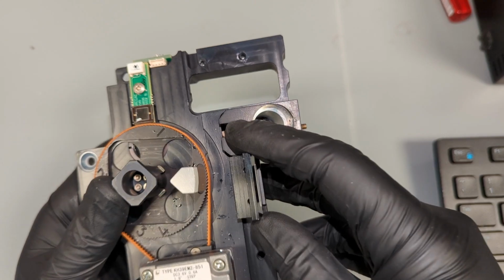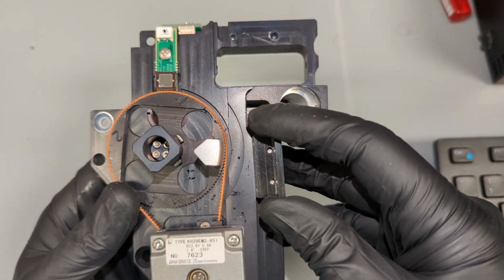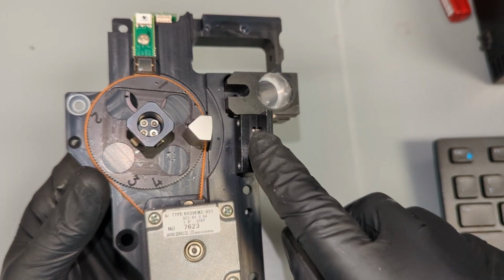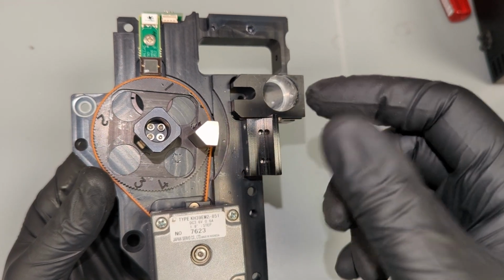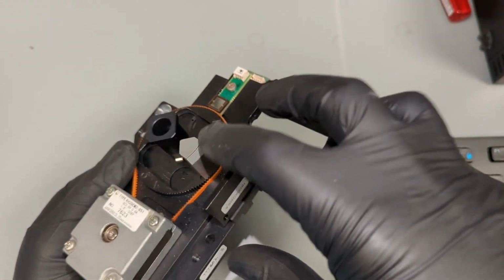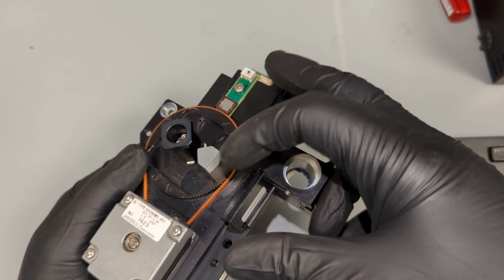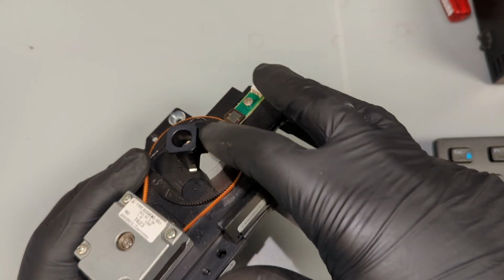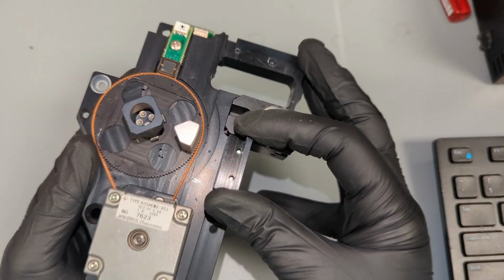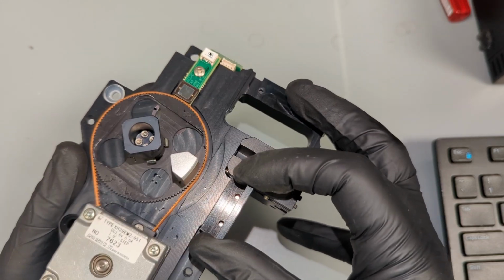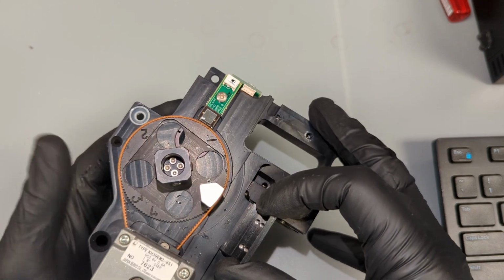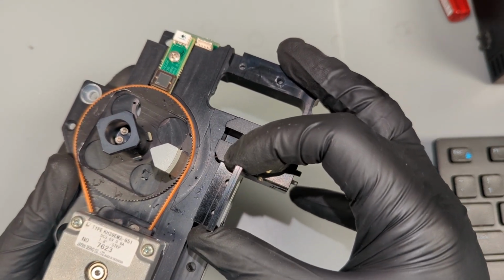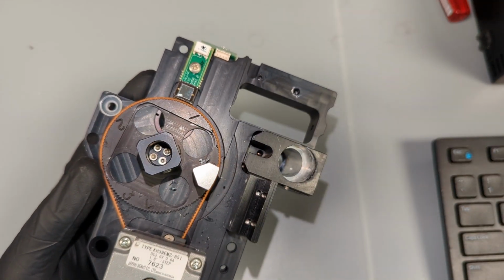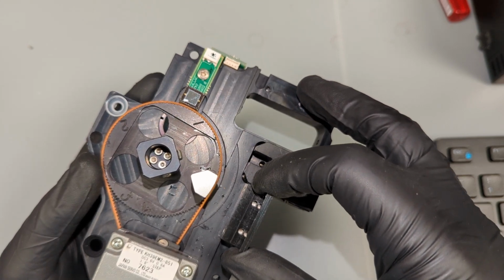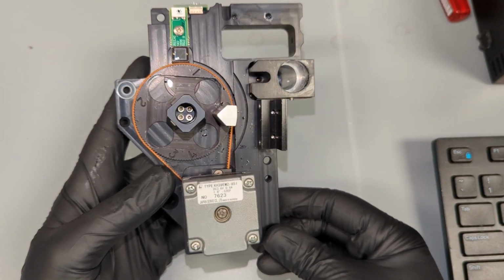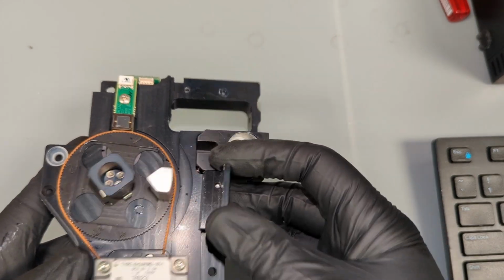Now, what can happen with these, and it's definitely happened with our instruments, you can see here that you can actually adjust the angle and positioning of this. And again, try to picture this. There is a daughter board here with a barcode reader IC there. So it will emit infrared light that will bounce off of this white plate or the barcodes, and then will be reflected back to this IC that will read either the barcode or this white homing tape. Now, again, this can be adjusted and positioned, and sometimes what will happen is this mirror module will start acting up and it'll start throwing errors. It won't be able to home itself, and it will be because this needs to be adjusted. It could be that the barcode reader IC has gone bad and died, but it's most likely that this needs to be adjusted.